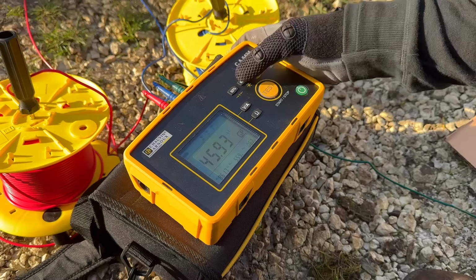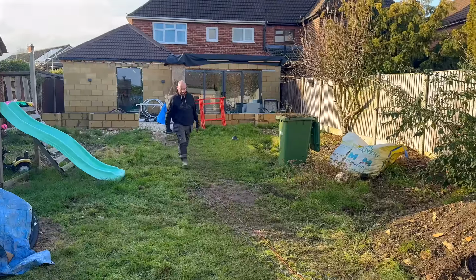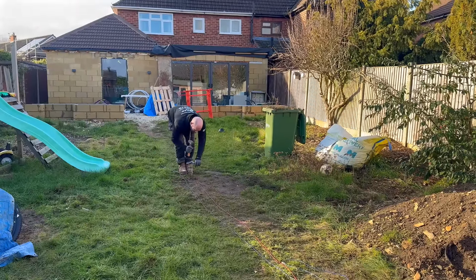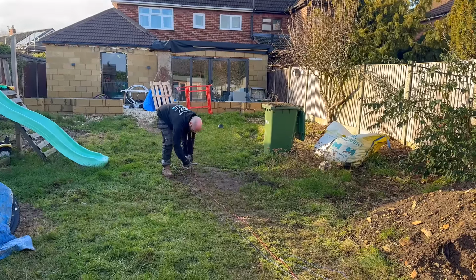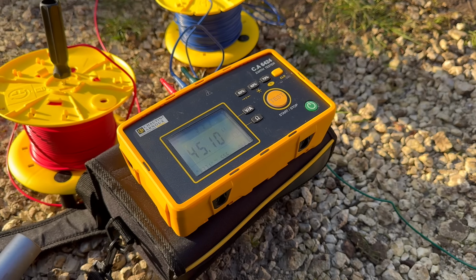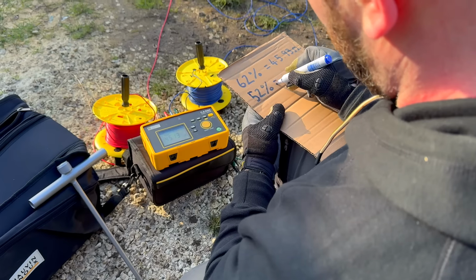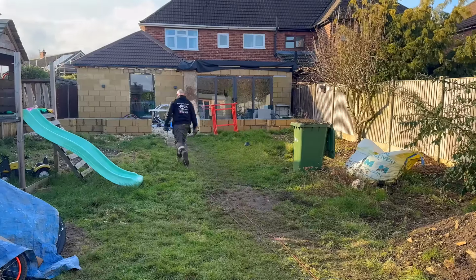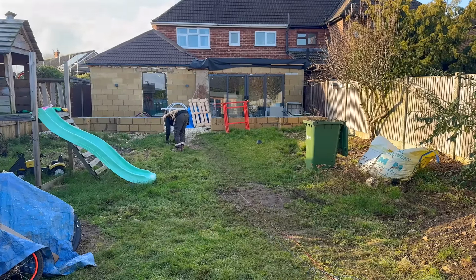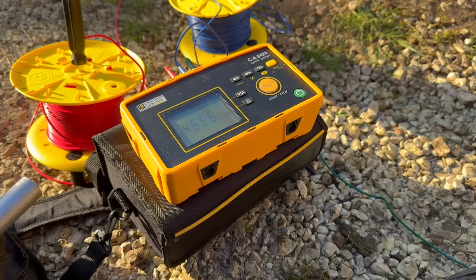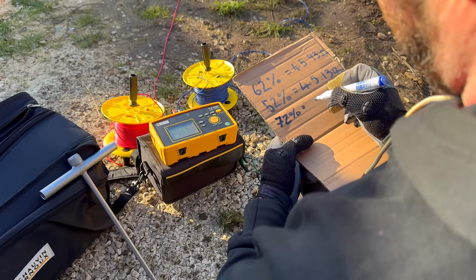We take the reading and record it. Next, we move the potential probe closer to the electrode to 52% of the distance. That's 11.4 meters from the earth electrode. That gives us a second reading. Then we move the potential probe further away to 72% of the distance. That's 15.4 meters from the earth electrode, and take the third reading.